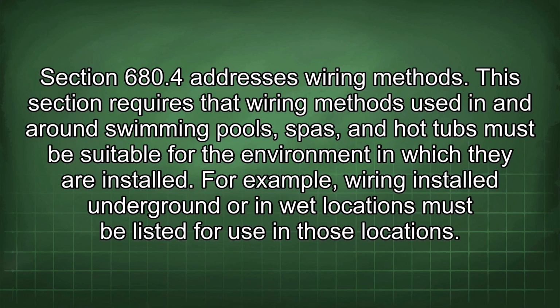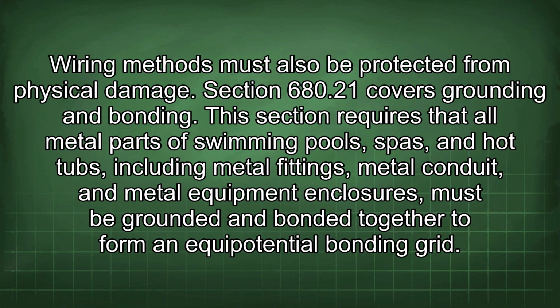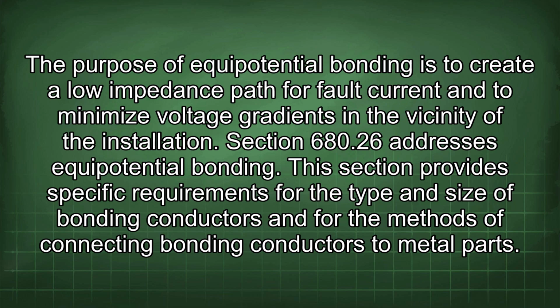For example, wiring installed underground or in wet locations must be listed for use in those locations. Wiring methods must also be protected from physical damage. Section 680.21 covers grounding and bonding. This section requires that all metal parts of swimming pools, spas, and hot tubs, including metal fittings, metal conduit, and metal equipment enclosures, must be grounded and bonded together to form an equipotential bonding grid. The purpose of equipotential bonding is to create a low impedance path for fault current and to minimize voltage gradients in the vicinity of the installation.